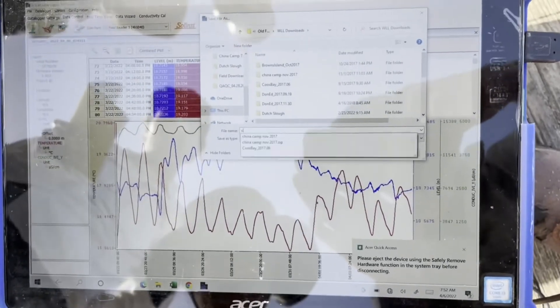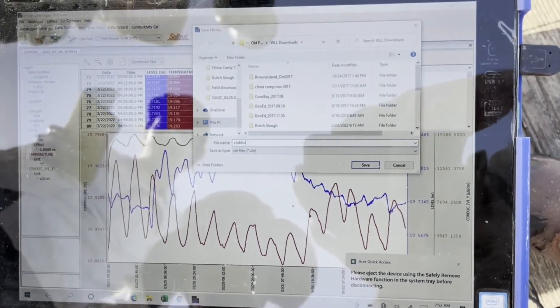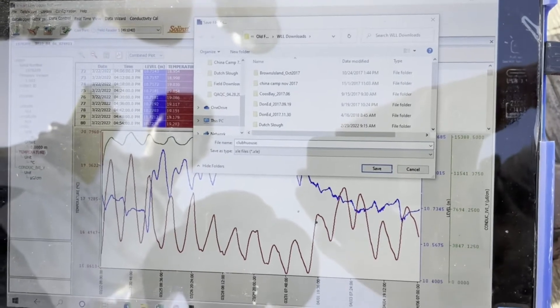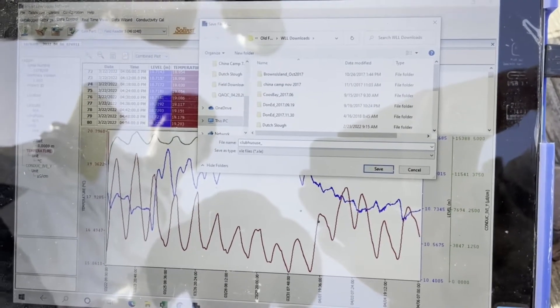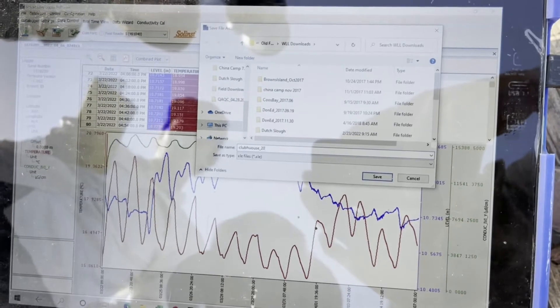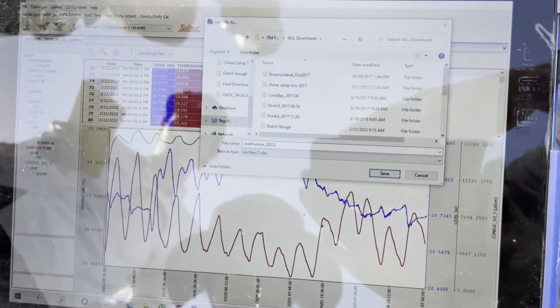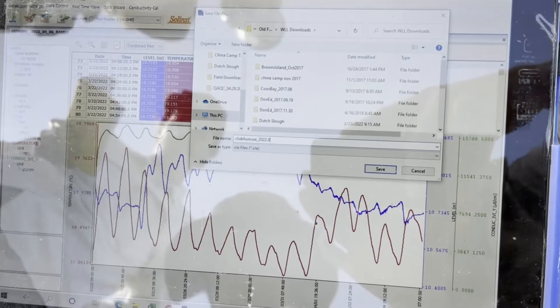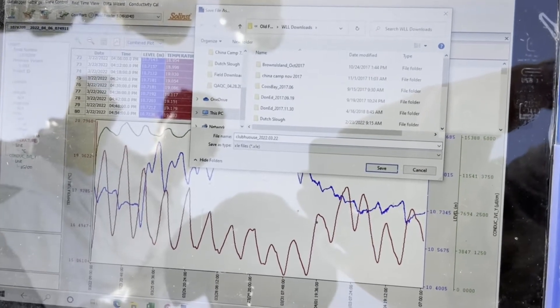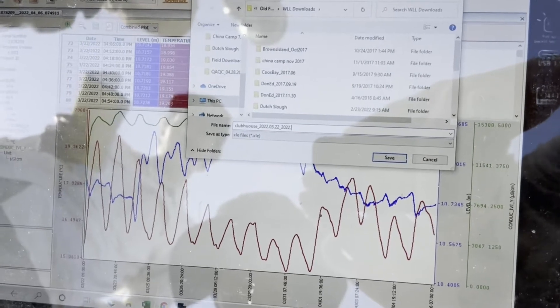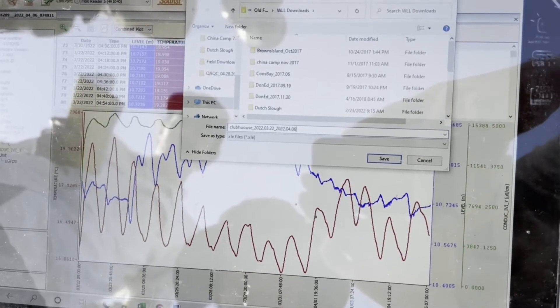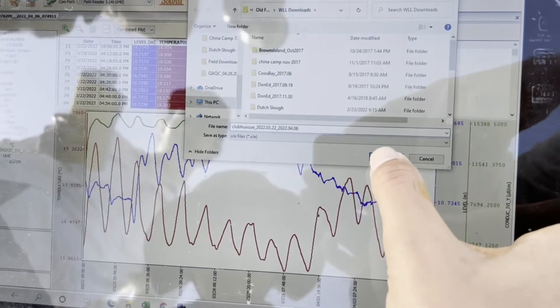This is the XLE file, which is the level logger file. Then I'm going to type the name in here. You type the name of your file. So we save them as the name and then the date, 2022-03-22. The date range - so this was deployed on the 22nd and then we're picking it up and downloading it on April 6th. Then we hit save.